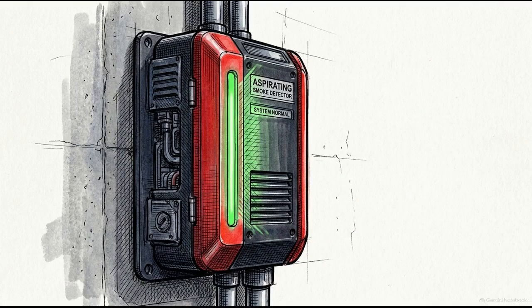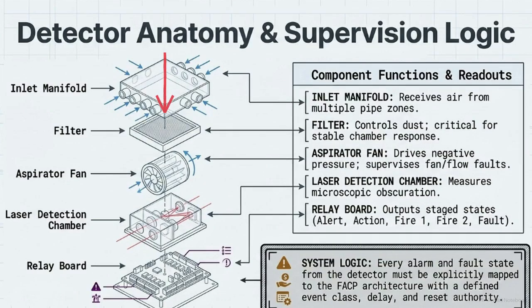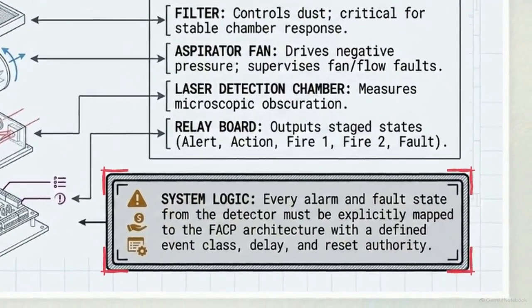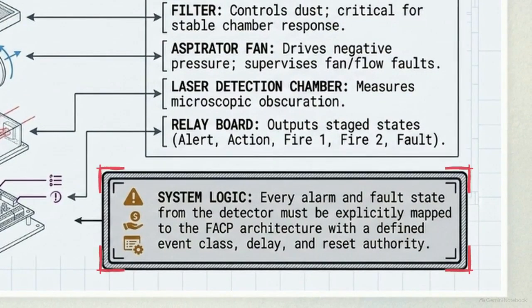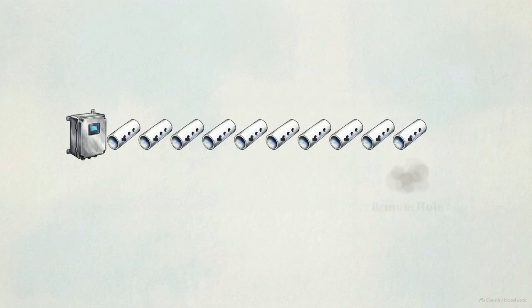Inside the detector cabinet, the captured air is processed to detect microscopic particles long before they become visible to the human eye. The internal stacking includes a particulate filter for reading stability, an aspirator fan to drive the negative pressure, and a laser chamber for sensing. Every internal fault from these components must be mapped to the life safety panel with a defined event class and reset authority. This sensing must overcome the reality of single-hole dilution.